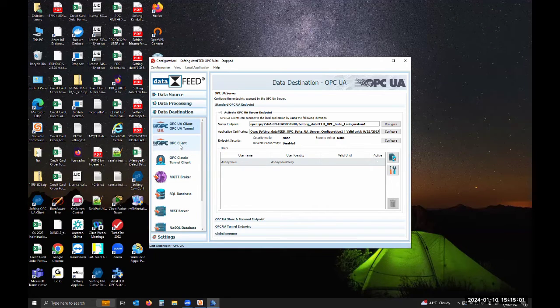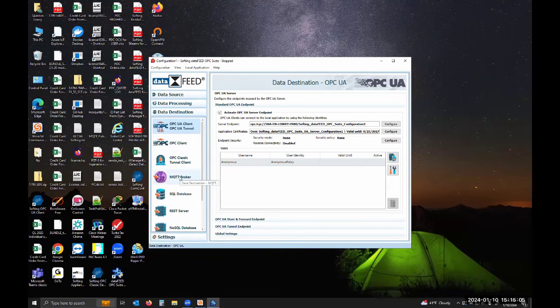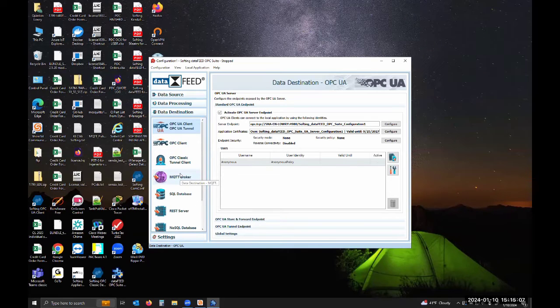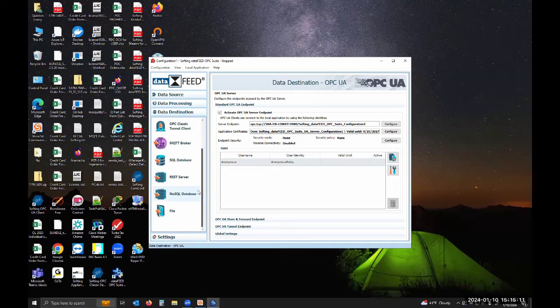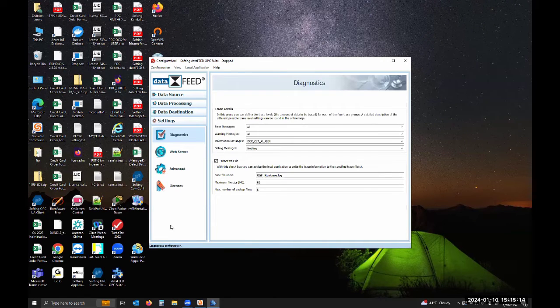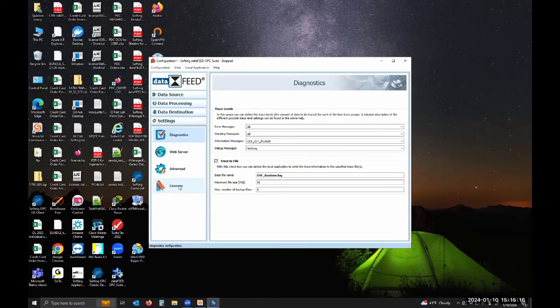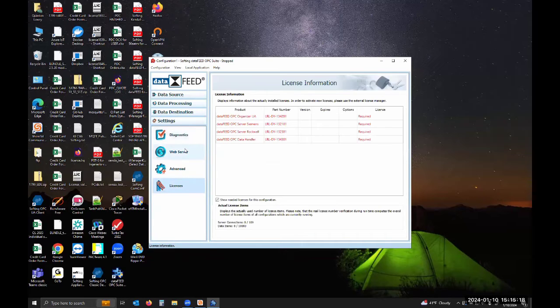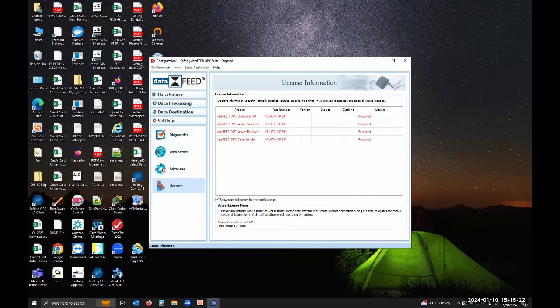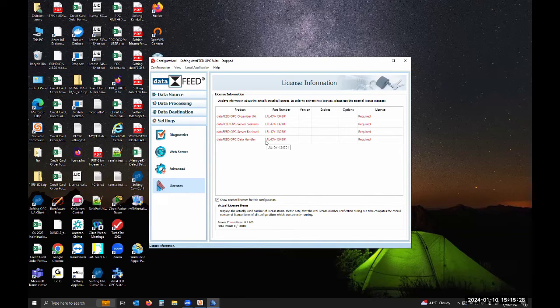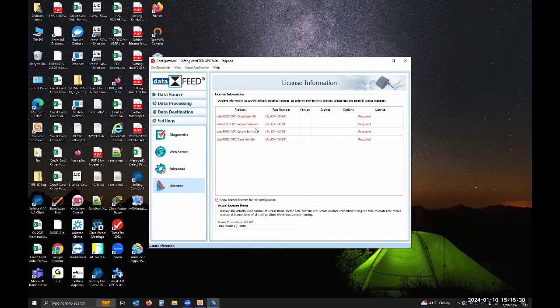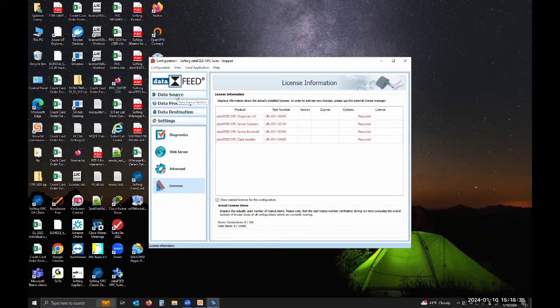This would be reading data from a Rockwell PLC and I want to make it available via OPC UA. The data feed suite itself will act as an OPC UA server. You can see there's a lot of options. You can act as a classic OPC server as well and send data to MQTT broker, a database, files, all kinds of things. Under settings, you can go to licenses and depending on your configuration, you can check box this and it'll tell you what part numbers you need to order.